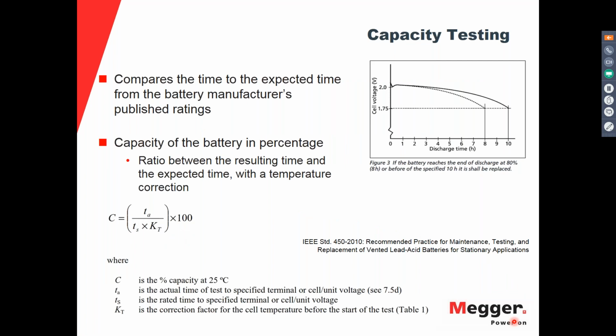So the capacity calculation actually compares the time that it took for the battery to reach that voltage to the expected time from the battery manufacturer's published ratings. This ratio is the capacity. So here you see the formula from the IEEE standard. You have TA, which is the actual time of the test. You have TS, which is the expected time. And I mentioned a correction factor for temperature. So here's the correction factor for that temperature. And we're going to see the table that contains the correction factors later.